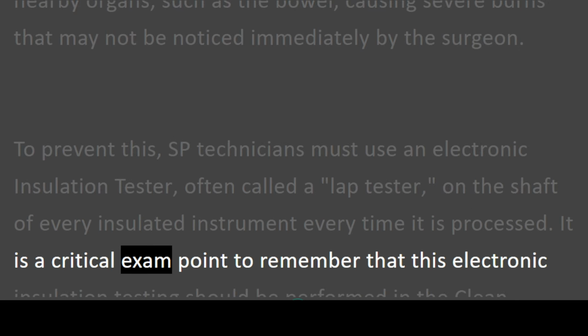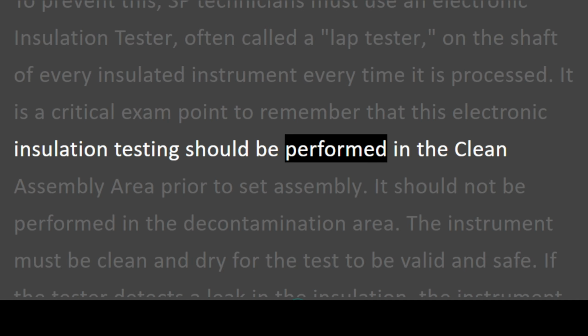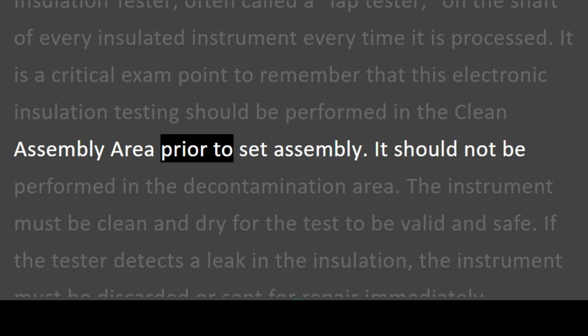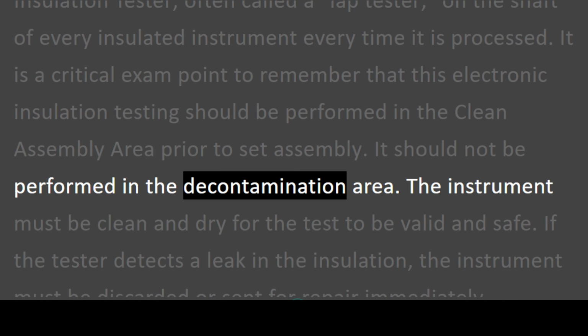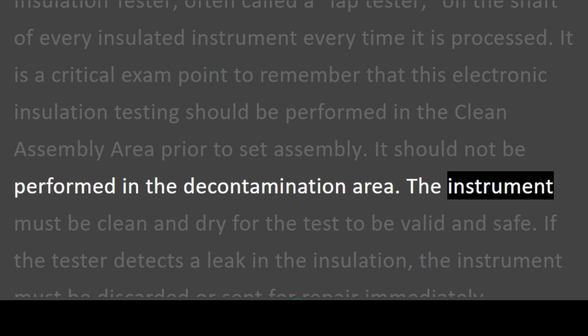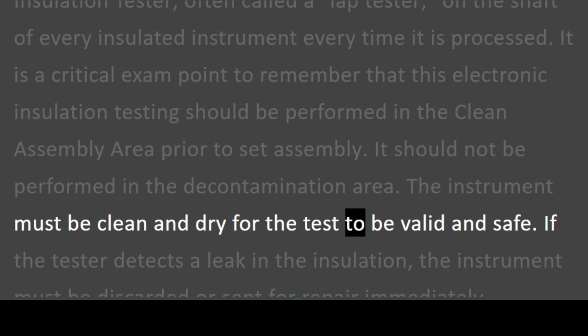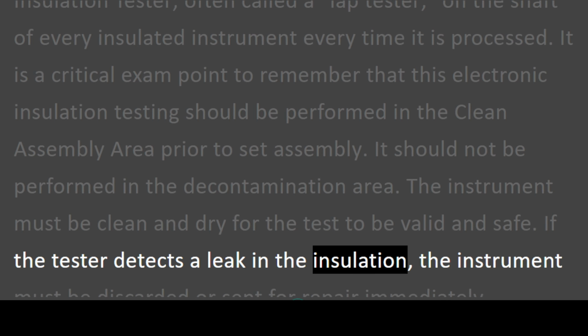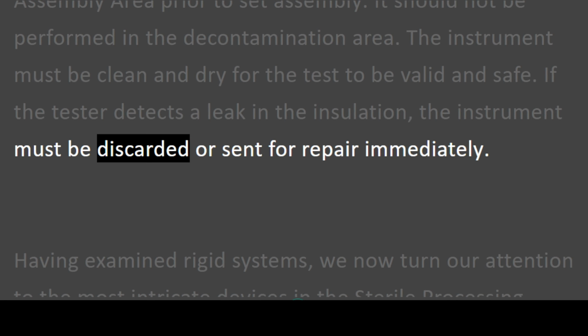It is a critical exam point to remember that this electronic insulation testing should be performed in the clean assembly area prior to set assembly. It should not be performed in the decontamination area. The instrument must be clean and dry for the test to be valid and safe. If the tester detects a leak in the insulation, the instrument must be discarded or sent for repair immediately.